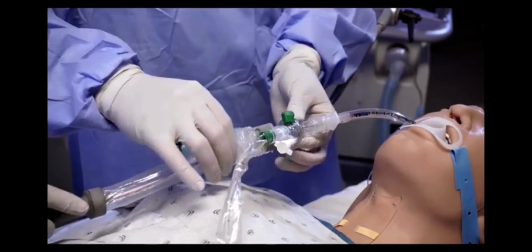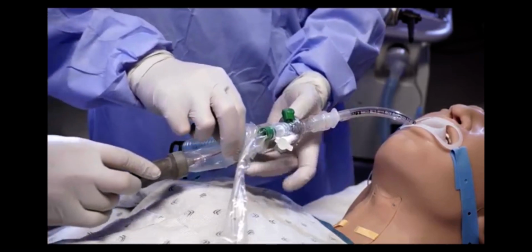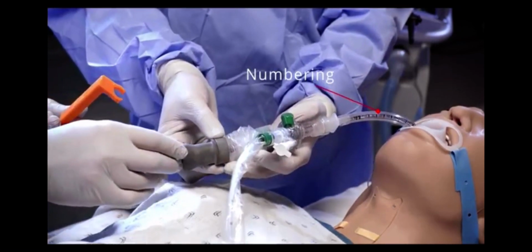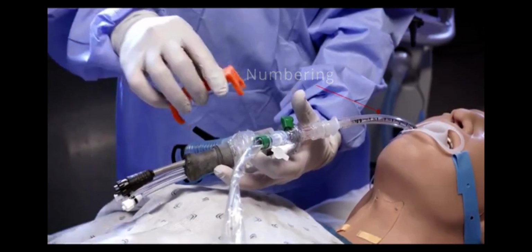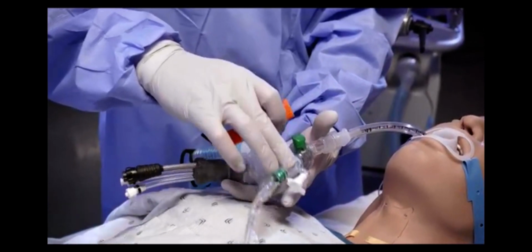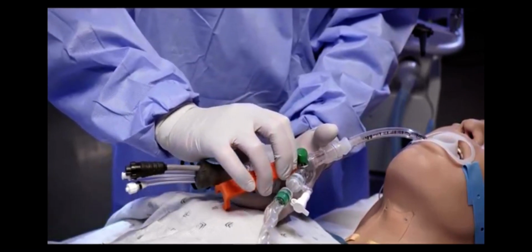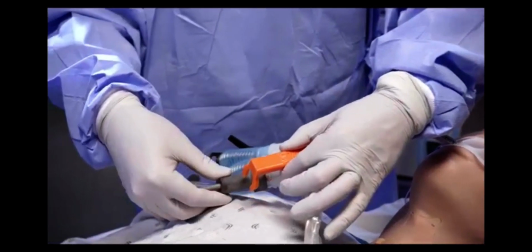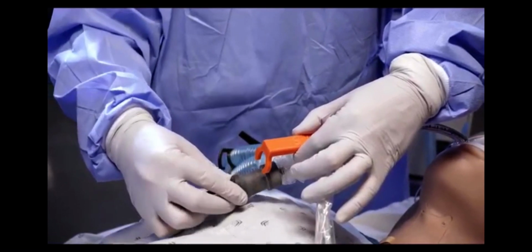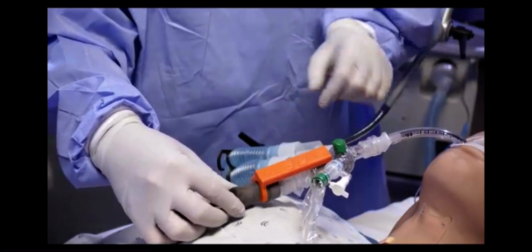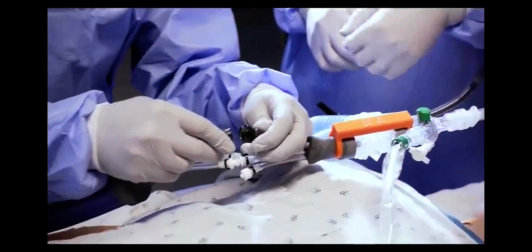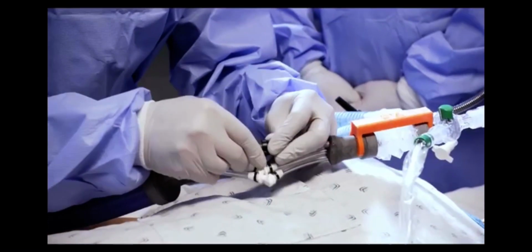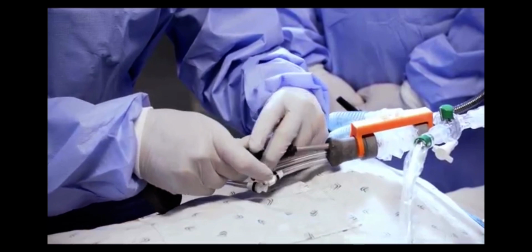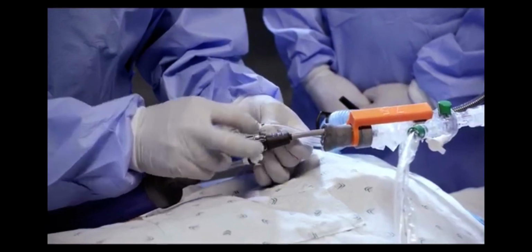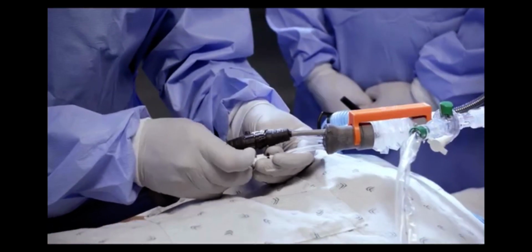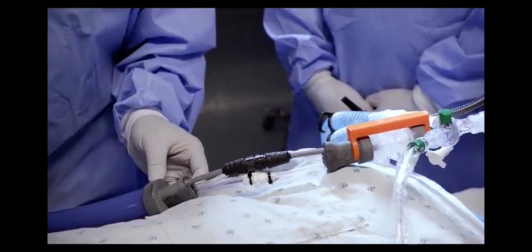There are two ways to determine that this is happening. Number one is to look and see if the numbers align with the numbering of the ET tube. And the second is to use the clamp that is provided in order to make sure that the device sits properly. Note that the clamp needs to be attached to the plastic piece at the distal end of the catheter in order to ensure that the device stays in place throughout the duration of the 20 minutes of light delivery. Once the device is into the patient, only then is the umbilical connected to the light catheter device.